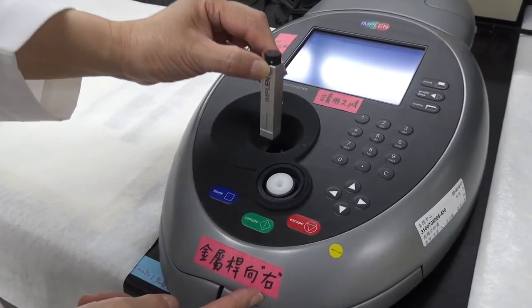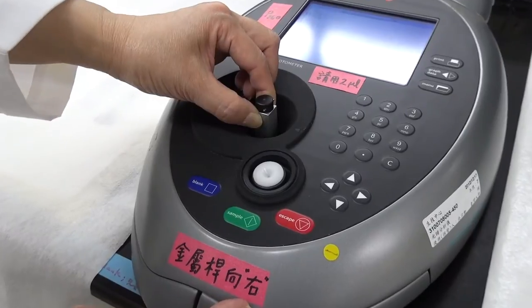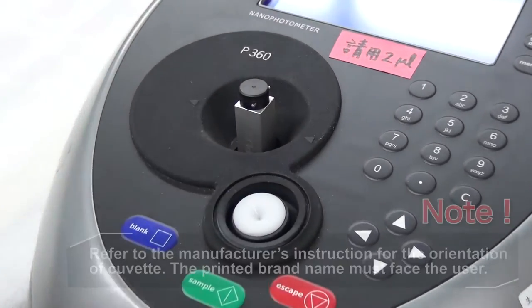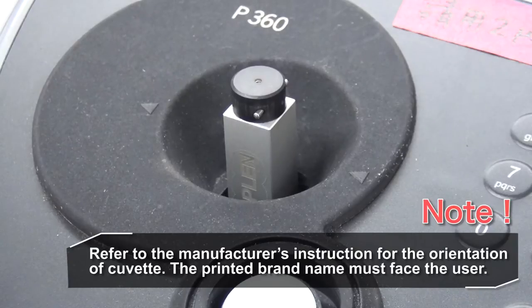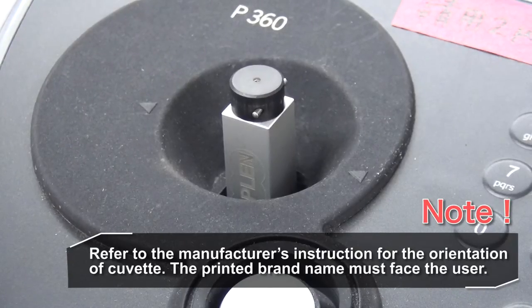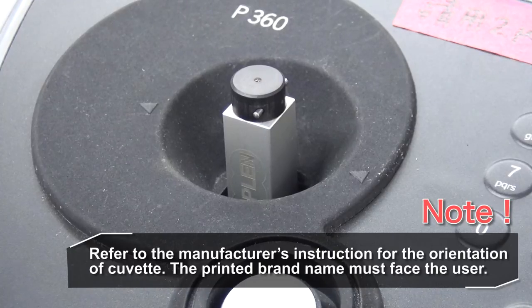Note, the light source shines from right to left. The clear side of the cuvette must be perpendicular to the incoming light. Please refer to the manufacturer's instruction for the proper orientation of the horizontal metal bar on the cuvette. The printed brand name must face the user.